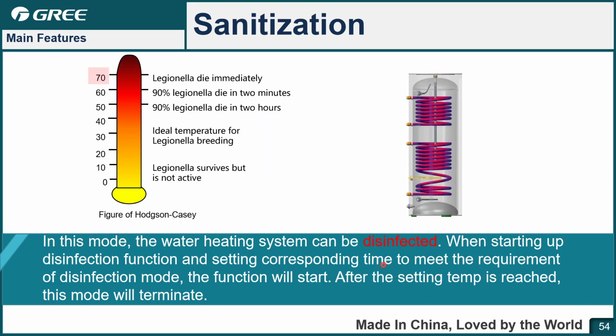Next one, sanitization. This is the disinfection function. After the tank has been used for a long time, maybe there are some bacteria inside. You can set the sanitization to heat the water to about 70 degrees Celsius. At this temperature, most of the bacteria will die immediately, so the water will be disinfected to keep it clean and healthy.